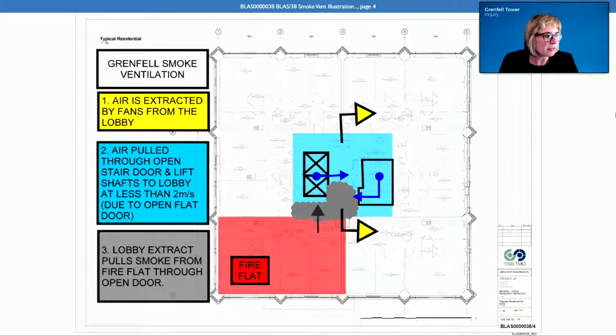Absolutely, because that's part of the test. As we've established on this job, we're taking an on-site test as demonstration that the system achieves the objective. Part of that test involves a process where you have a certain number of doors open while performing this 2 meters a second test. So you've actually taken that into account.